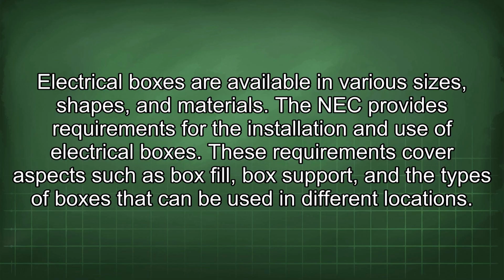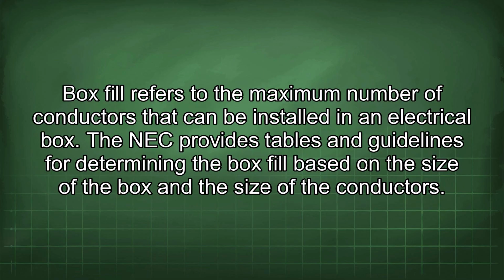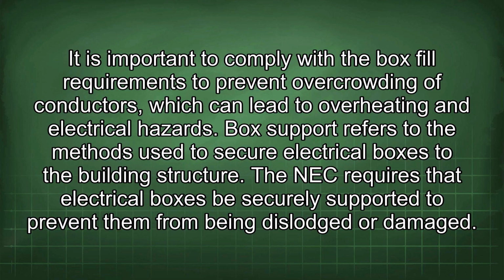Box fill refers to the maximum number of conductors that can be installed in an electrical box. The NEC provides tables and guidelines for determining the box fill based on the size of the box and the size of the conductors. It is important to comply with the box fill requirements to prevent overcrowding of conductors, which can lead to overheating and electrical hazards. Box support refers to the methods used to secure electrical boxes to the building structure.